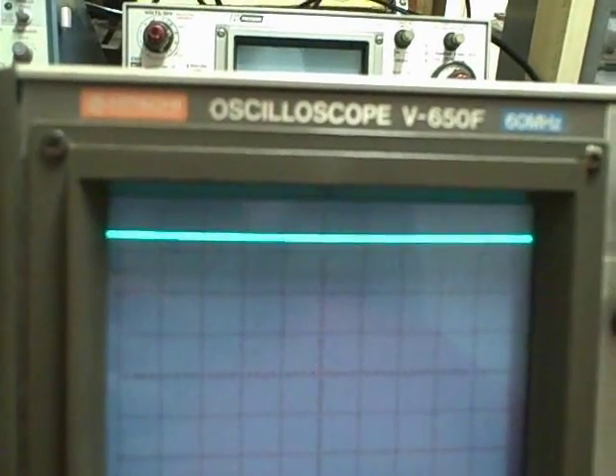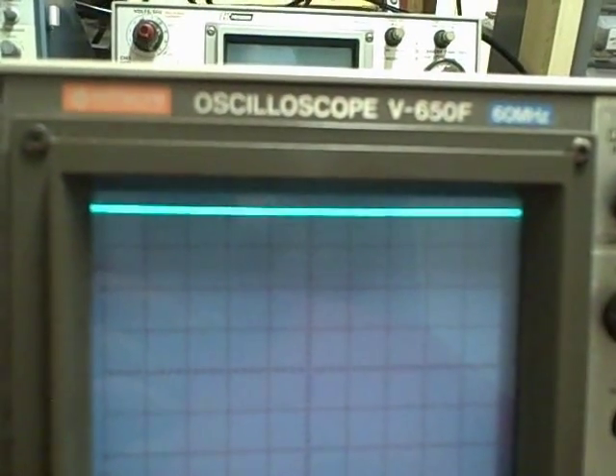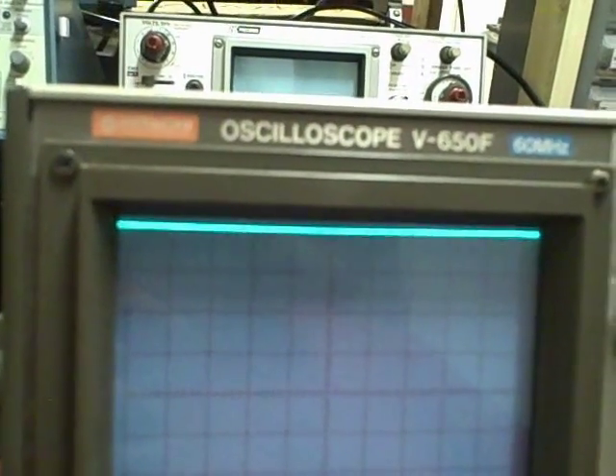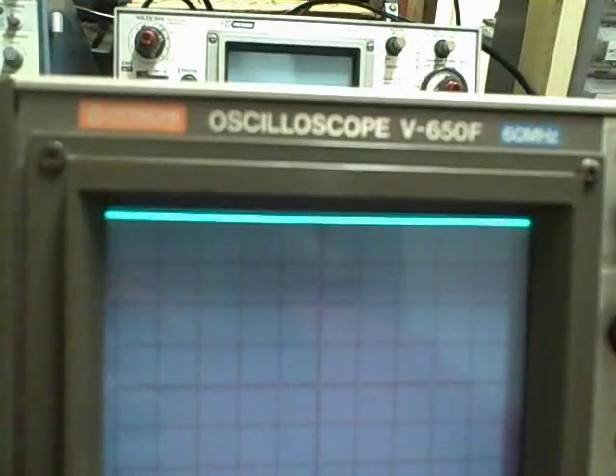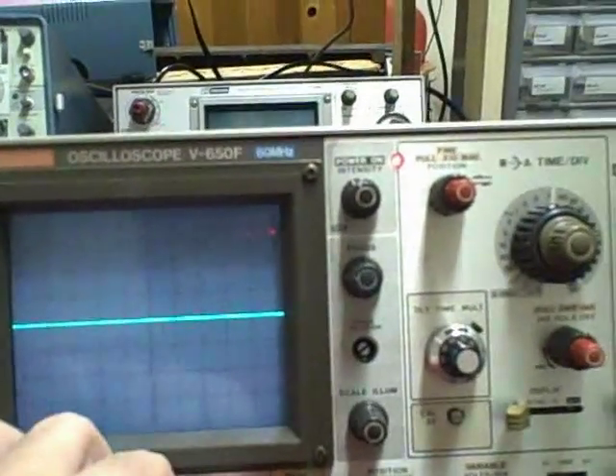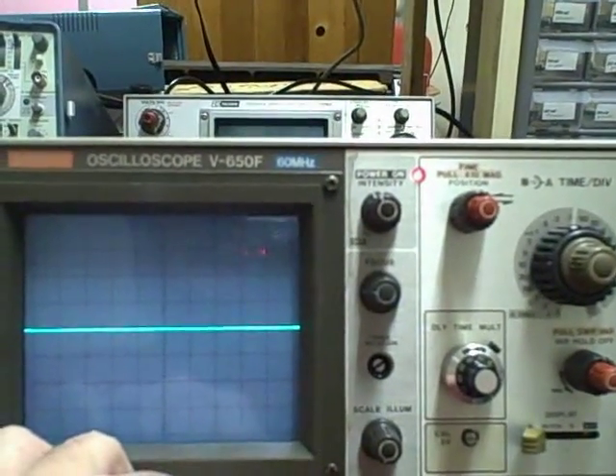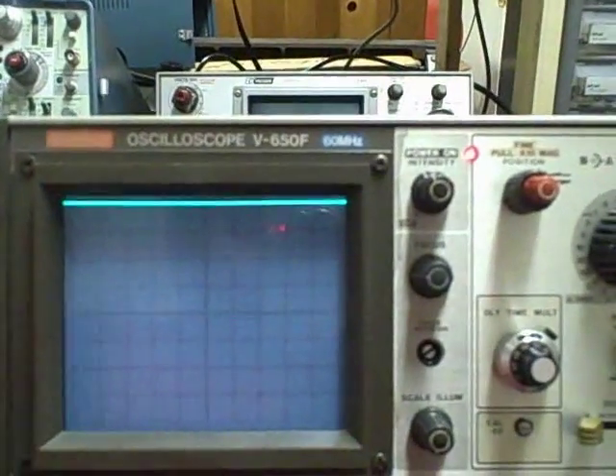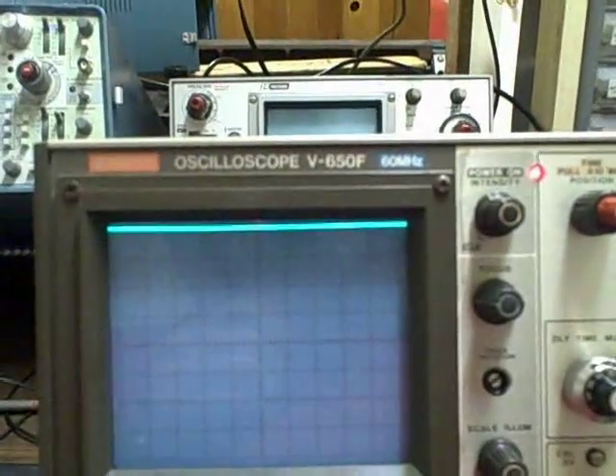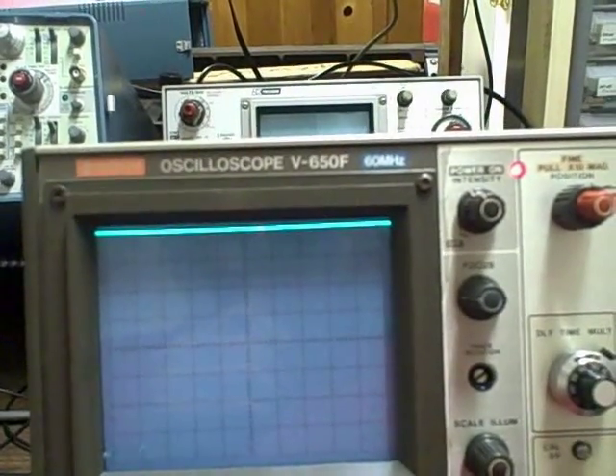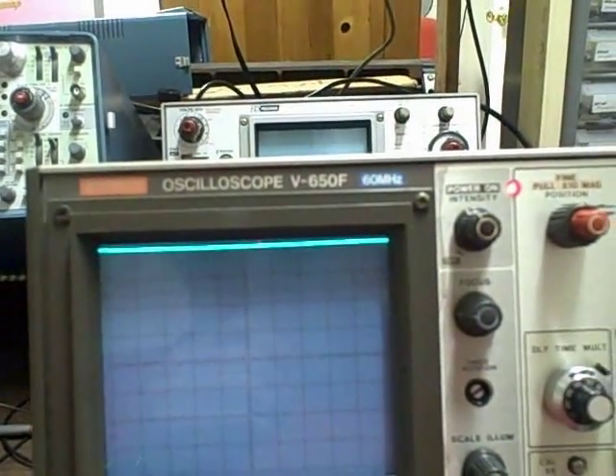And maybe we can kick her up a little bit more and go for 20. Let's check our zero once again, make sure we haven't drifted. Zero's good. Full scale looks pretty good. All right. We are running 19.91. We were within nine hundredths of a volt of being 20 volts at full scale.